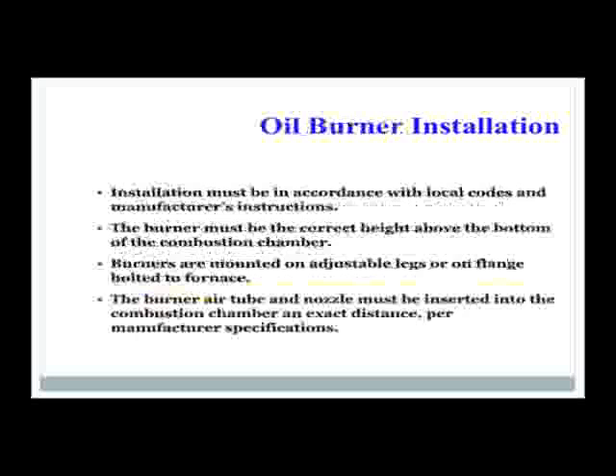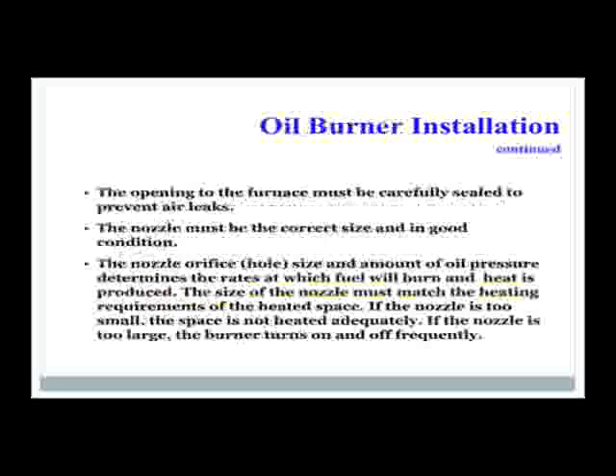The burner must be the correct height above the bottom of the combustion chambers. Burners are mounted on adjustable legs or on flanges bolted to the furnace. The burner air tube and nozzle must be inserted into the combustion chamber the exact distance per manufacturer specifications. The openings to the furnace must be carefully sealed to prevent air leaks. The nozzle must be of correct size and in good condition, and the nozzle orifice, that's the hole size, and the amount of oil pressure determine the rates at which the fuel will burn and the amount of heat produced. The size of the nozzle must match the heating requirements of the space. If the nozzle is too small, the space will not be heated. If the nozzle is too big, the burner will turn on and off frequently and decrease the life of the equipment.